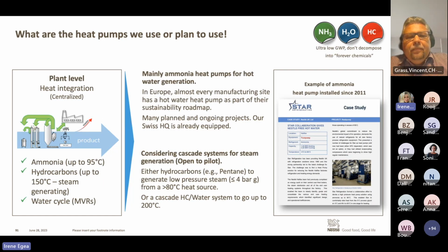And then at plant level, this is where most of the action happens. This is looking at the factory level, and this is where we have the biggest opportunities, to centralize and benefit from all the synergies we have. Quite often, the boiler house is next to the chillers, and we can do a lot with heat pumps. So we have been using ammonia heat pumps for many years. I just gave here an example of a factory in Halifax in the UK that has had a heat pump installed since 2011, an ammonia heat pump that generates the hot water and replaced a coal boiler. So that was a good move.